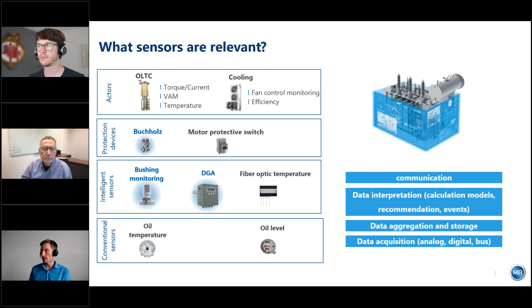I don't think there's another system that also takes into account the accuracy of the sensor. For example, when I talk to customers, they had problems with bushing monitors giving false alarms. But as Alexander said, we know the probabilities of that happening, so we can take this into account, and it will show if this is a false alarm and the data indicates it's not probable that the bushing has failed. This is why it's useful to have the system enabled, to look at the evaluation in order to get very accurate diagnostics and know the next step to assess and maintain the transformer.